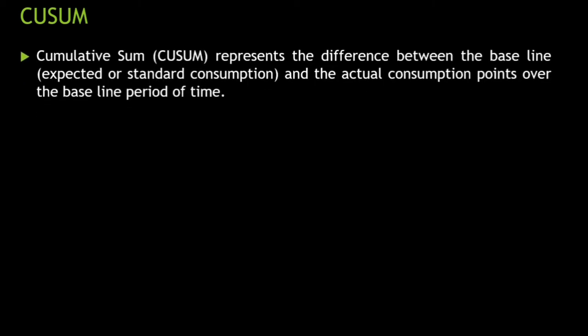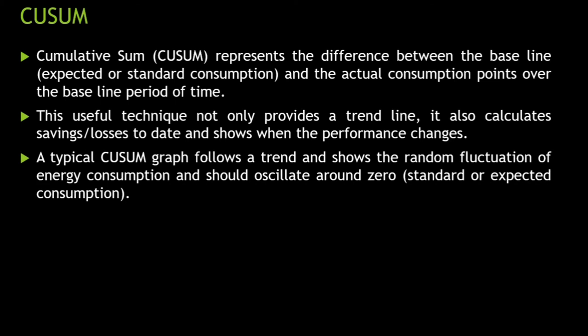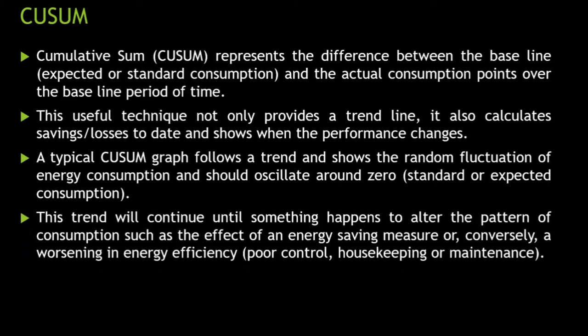Starting with what is this Cumulative Sum: CUSUM represents the difference between the baseline — that is the expected or standard consumption — and the actual consumption points over the baseline over the period of time. Once we cover the examples, you will come to know what it is exactly. This useful technique not only provides a trend line, it also calculates the savings and losses to date and shows when the performance changes. A typical CUSUM graph follows a trend and shows the random fluctuations of energy consumption and should oscillate around 0.